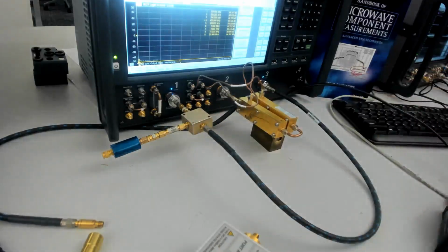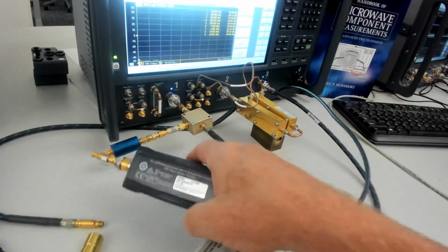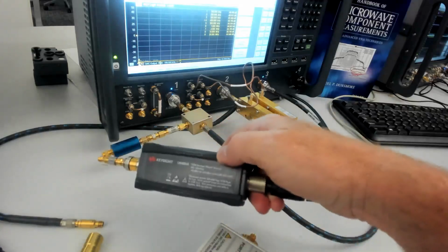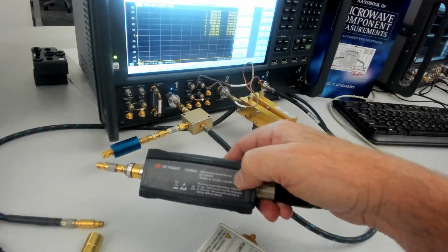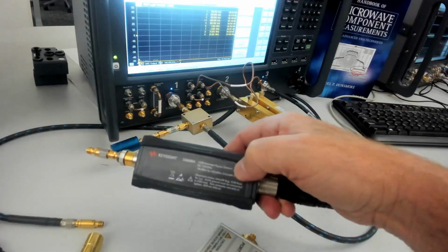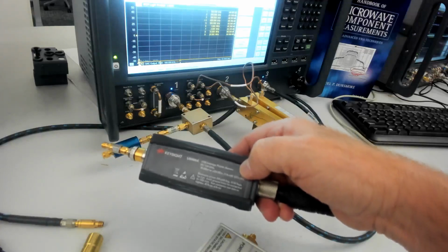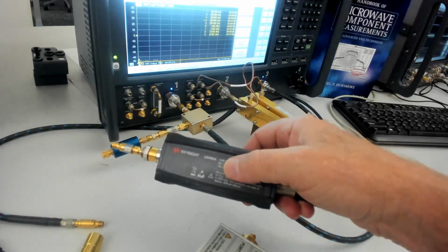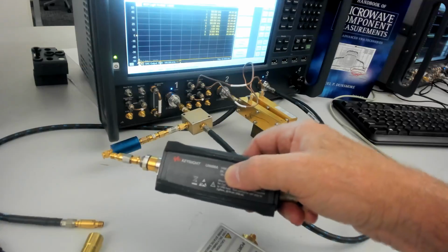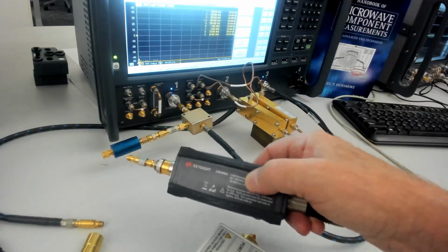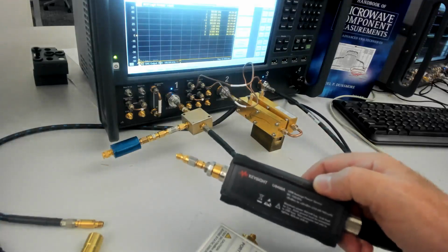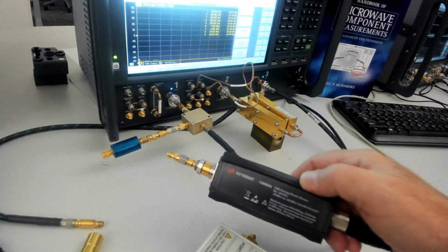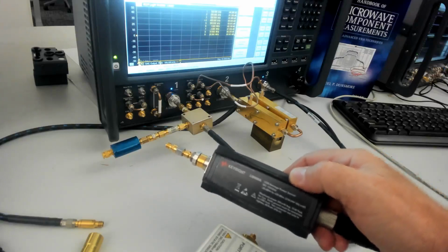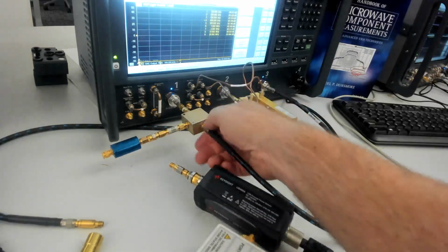And then later on, I'm going to use a power sensor. And again, I need a DC coupled one. Most of them go down to 10 megahertz. This is a new USB sensor, the U8489A. And yes, one of the advantages of Keysight is you can find lots of different things around when I work here. So this one happens to be the only DC one I had conveniently available, and it's a DC to 120 gigahertz power sensor. So I've had to adapt it, and at these really low frequencies, those adapters don't make any difference. So that will get me all the way down to DC for the power step. And here's my calibration mixer. We're going to take a first step of using the power meter. So let's go do the power meter step.